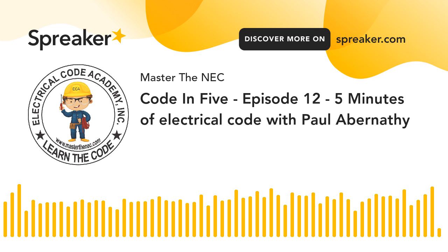Then number 10 is talking about direct burial. So if your tray cable is listed for direct burial, then it can go straight into the ground. It's okay. And then lastly, 11 talks about hazardous classified locations. Now, if somewhere else in the code, like maybe Article 501, 502, 503 of hazardous classified locations, they make reference to a tray cable application, then there you go. You're okay. As long as it's a specific type of tray cable, whether it's a hazardous location, HL classification, it's still tray cable. So it gives you the allowance to go to other locations.